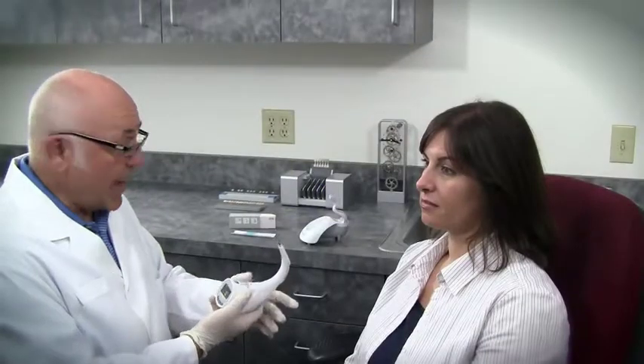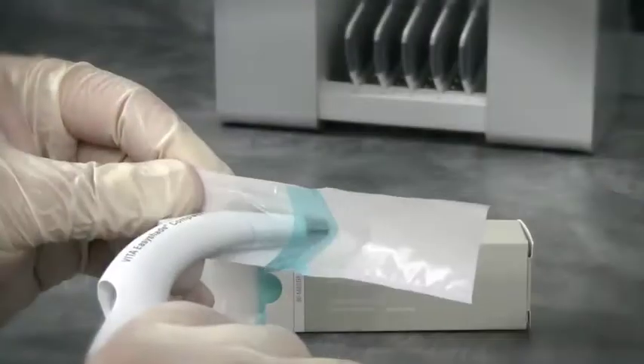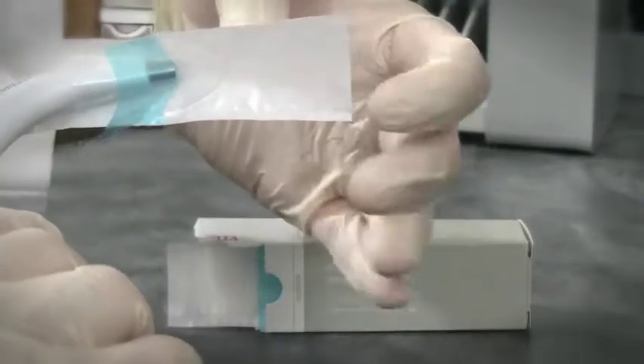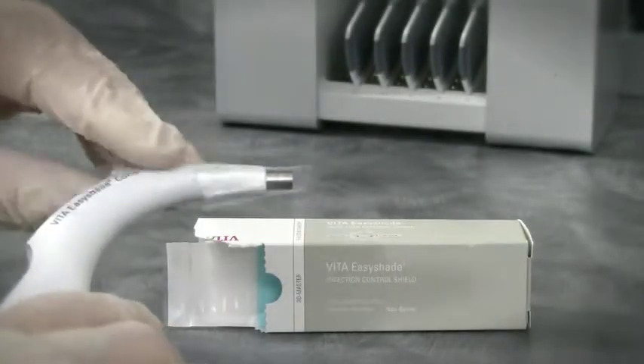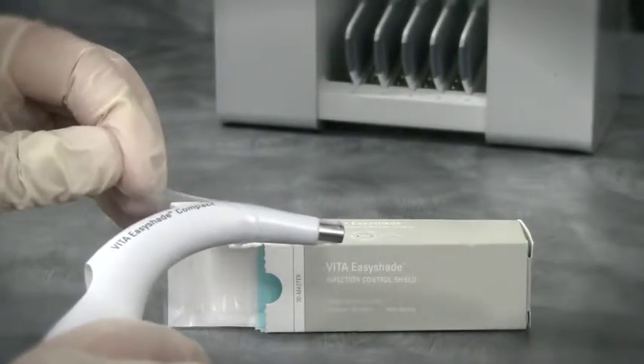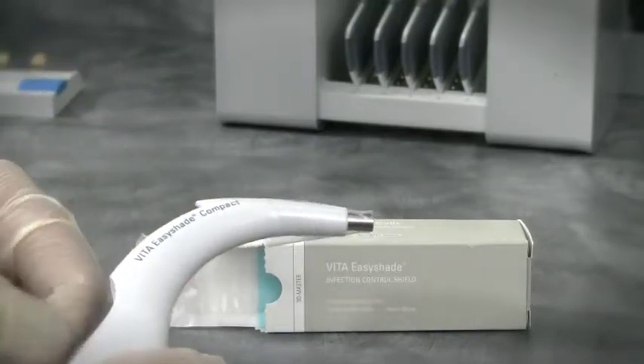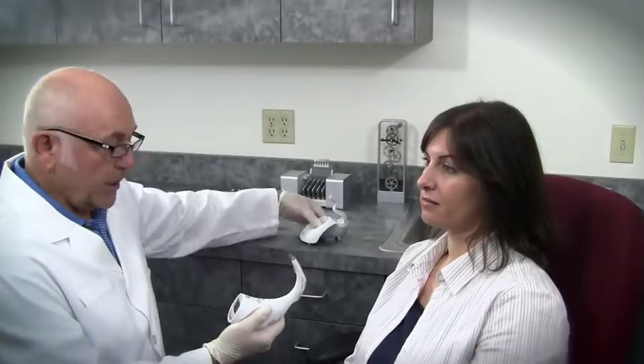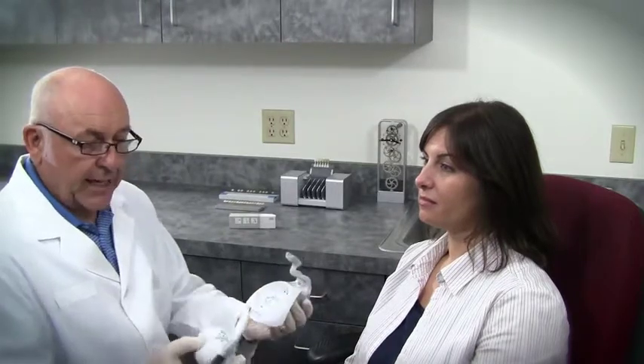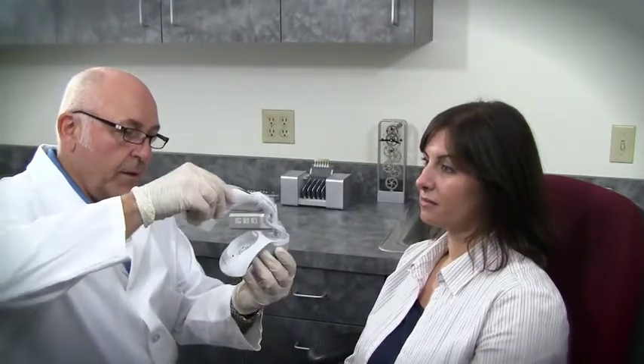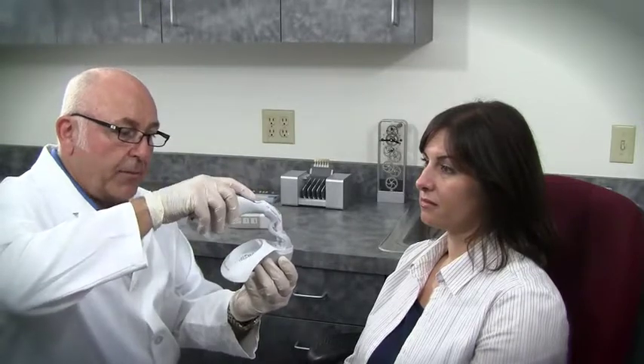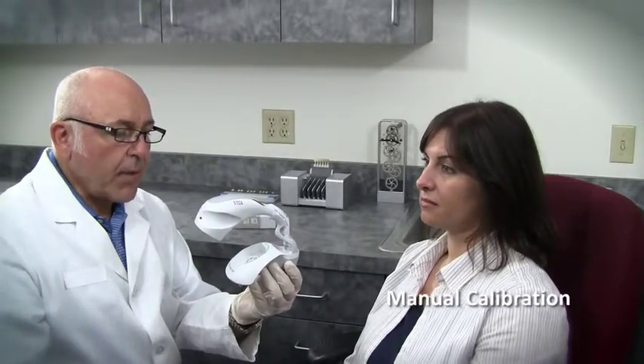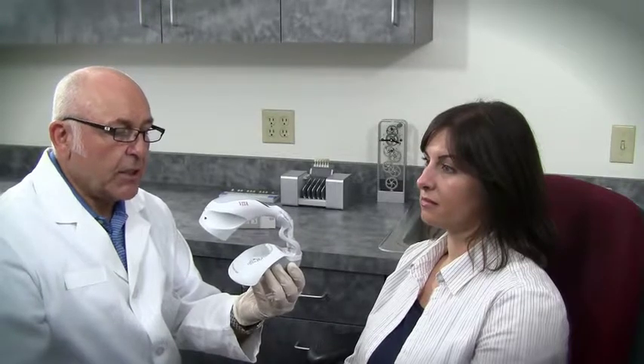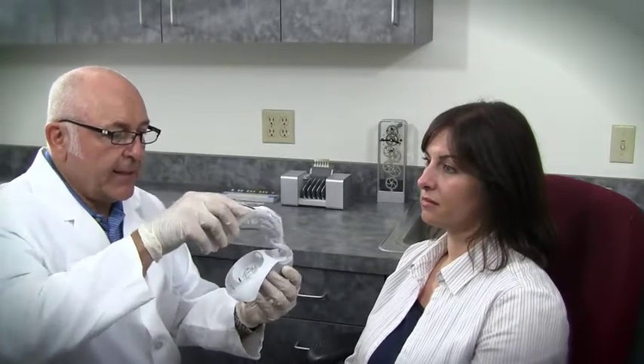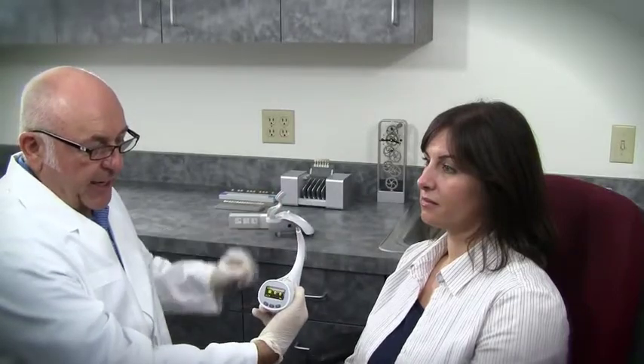Before doing so, I'm going to apply a cross-infection shield or barrier. And the pocket for this is located below the blue disposable wrapper. I tear it off and pull the shield tight over the hook like so. Now I'm going to calibrate the unit by placing it in the holder. And in this mode, in the manual mode, I depress the button and wait for the second flash and the tone. We've now calibrated and we are ready to take the patient's shade.